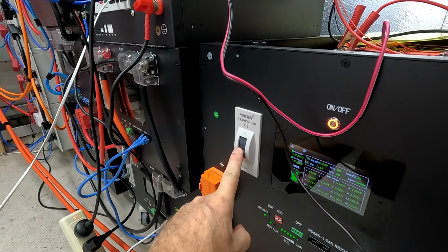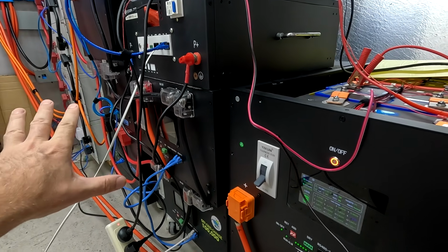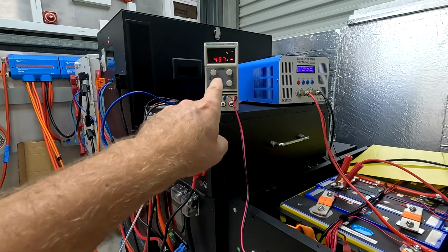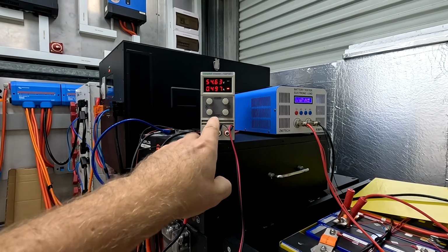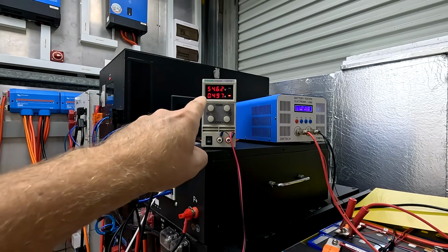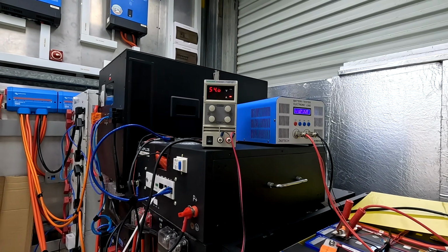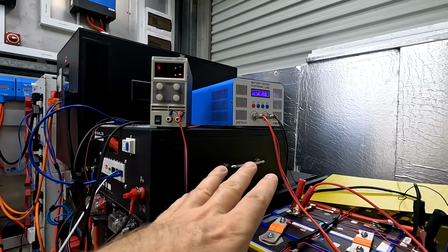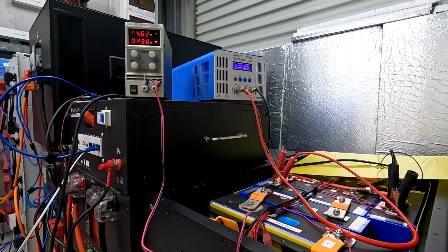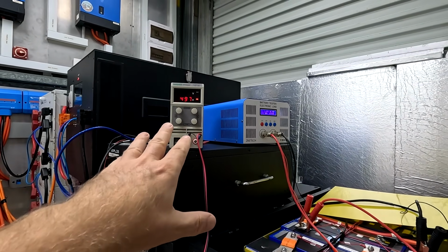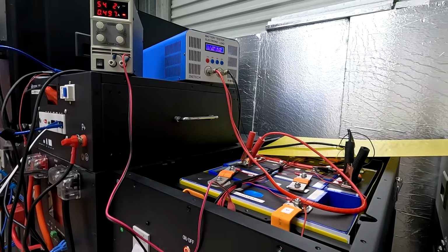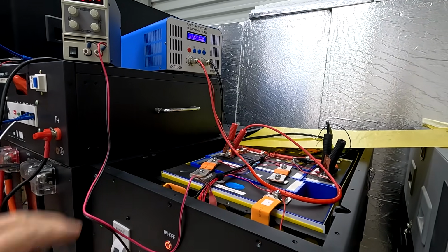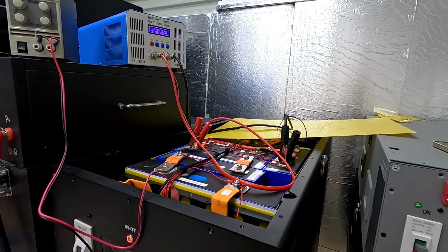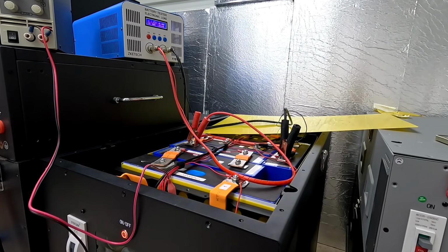I've also isolated the battery from the solar system now and charge it with the adjustable power supply to 55.2 volts with a very low current of around 500 milliamps only. If I go higher, the cells will go very close to 3.65, and then the BMS will turn off. So we leave it sitting at this half an amp only, which will keep the battery at 55 volts, ideal for the active balancer to do its work.